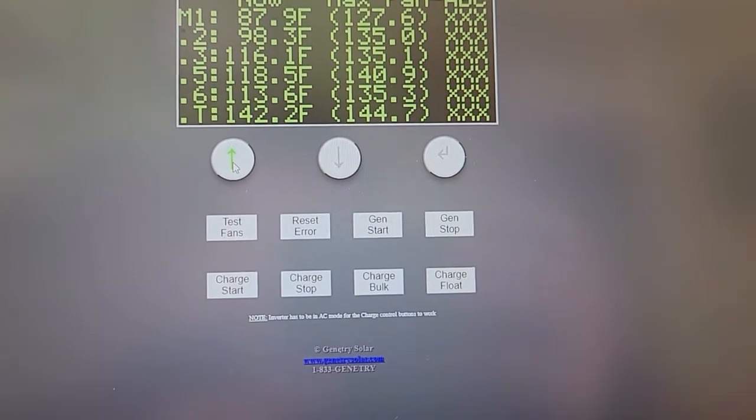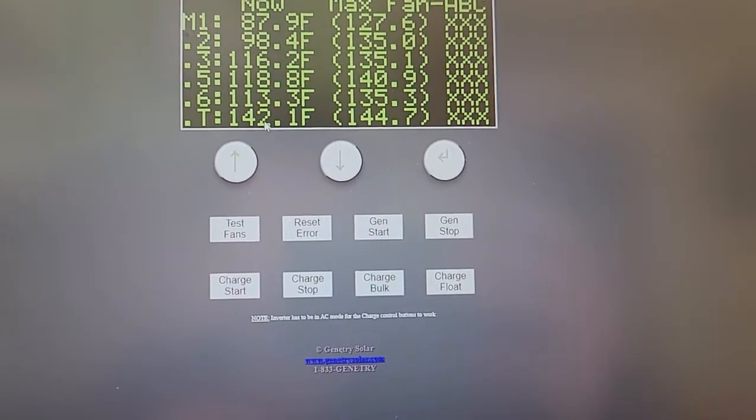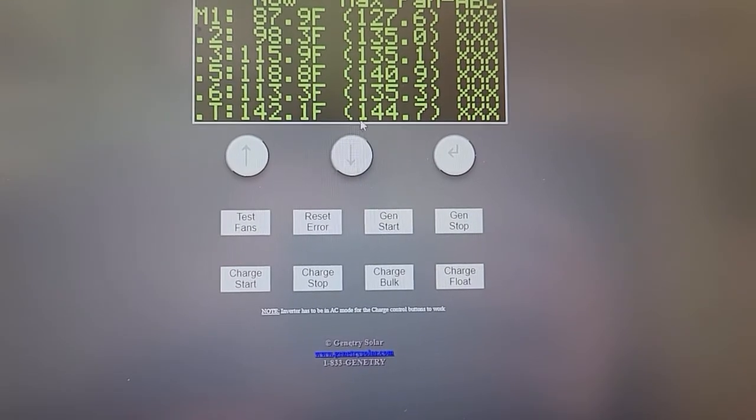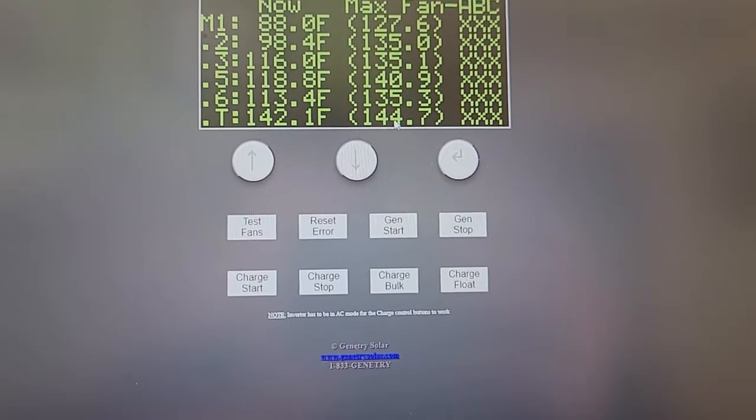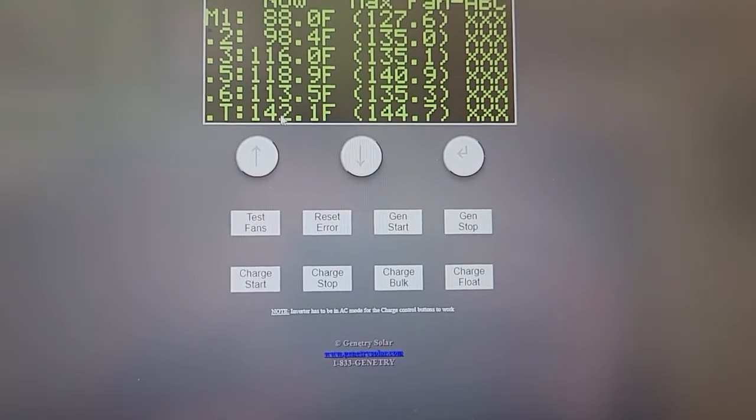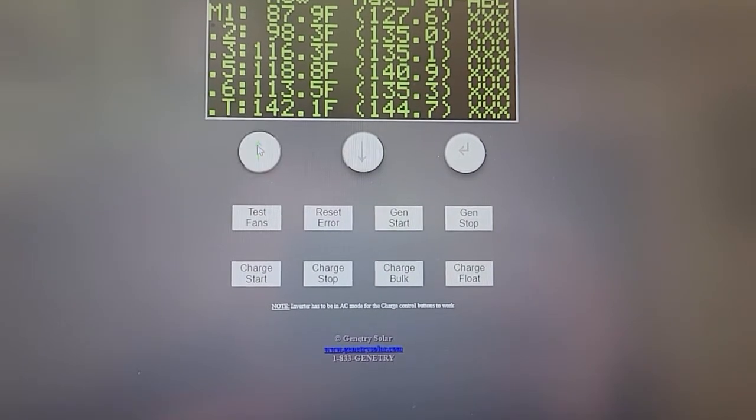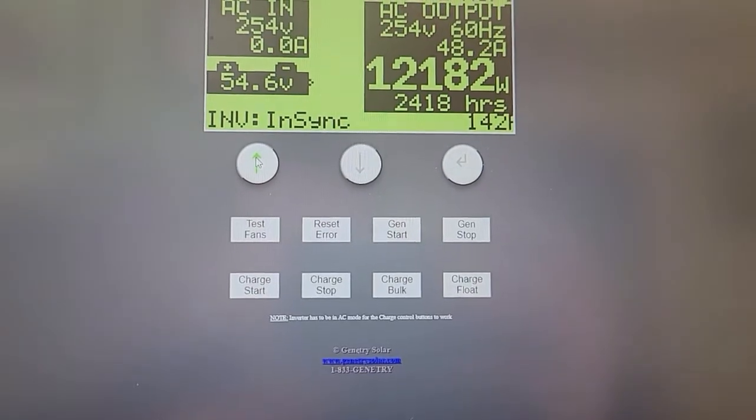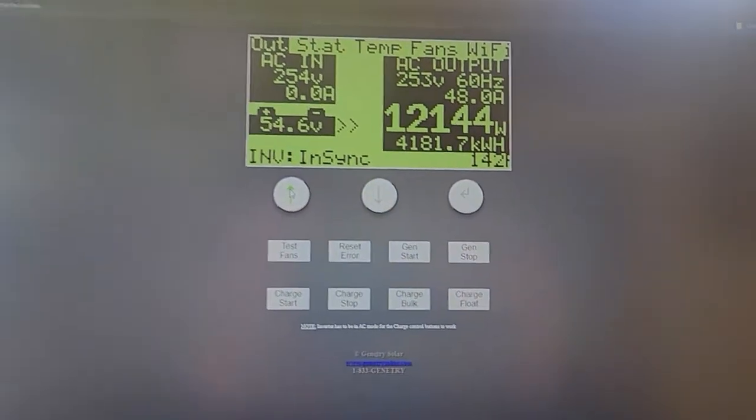And this has been running for 10 minutes. So if there was something going on where it was going to overheat, we would see this 142 continue to rise. But as the fans ramp up, coming from its 144 peak, then this temperature comes down. That means that the fans are managing the heat at 12 kilowatts. So that's an important number.